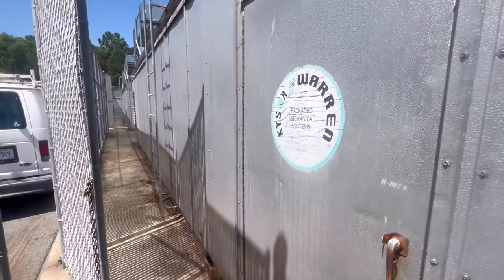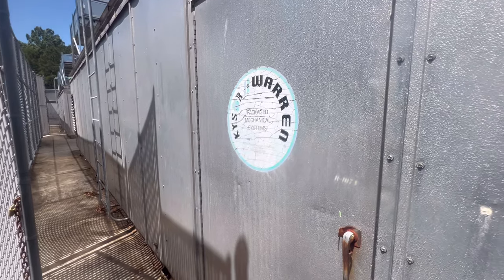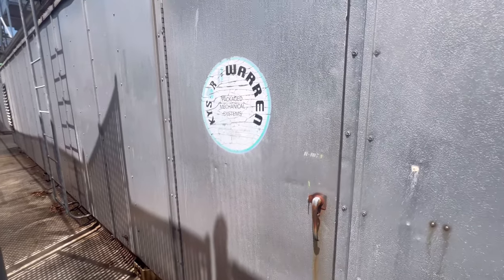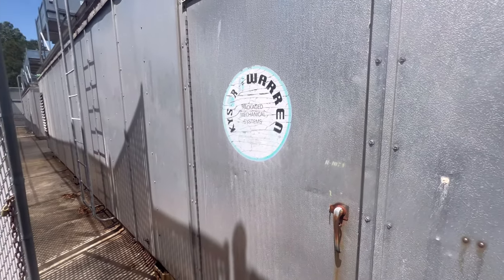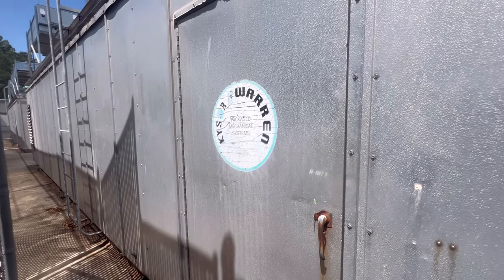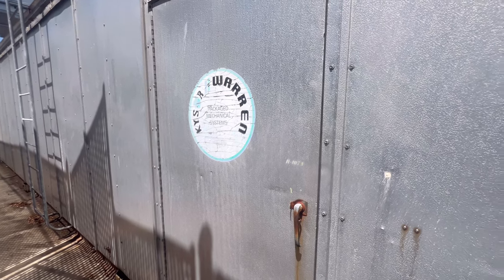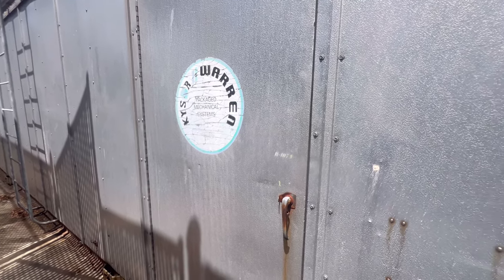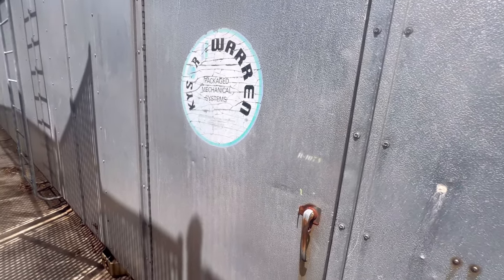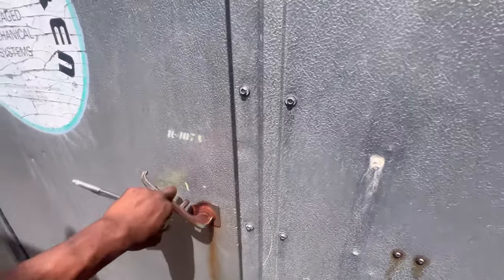What's up YouTube, I am at Walmart. We got two compressors off on oil. I already recently went in here, checked my reservoir - we got one ball floating. I checked my compressor's oil pot: got one at three-eighths filled halfway, and then the other one is all the way filled. Oil level is okay, so I need to go diagnose and see what's going on.